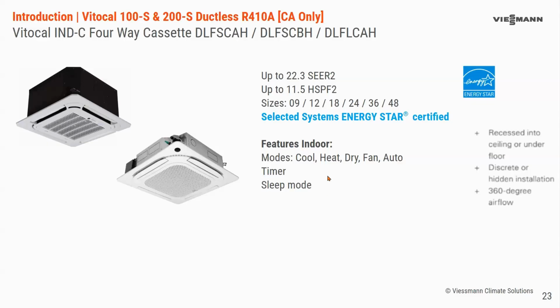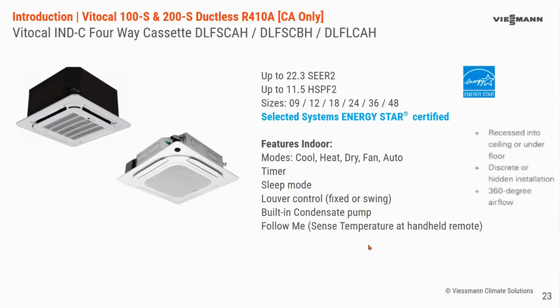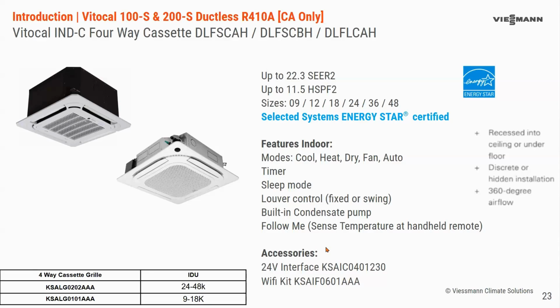same modes that you're going to see on all these indoor units. We have sleep mode and timer, which is also on the high wall. Louver control, you can set fixed or swing. Since these are in the ceiling, concealed, there is a built-in condensate pump included to help you move that condensate out. Follow Me is a standard feature with all of the indoor units that have the handheld remote. And then again, you have your 24-volt accessory and your Wi-Fi kit.